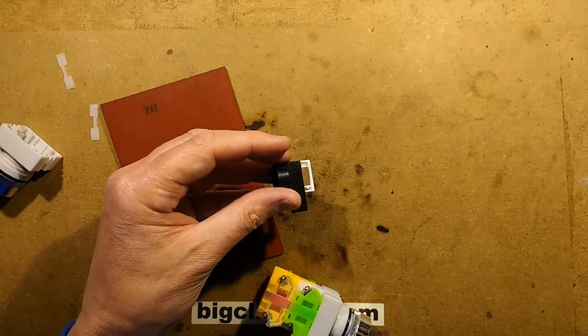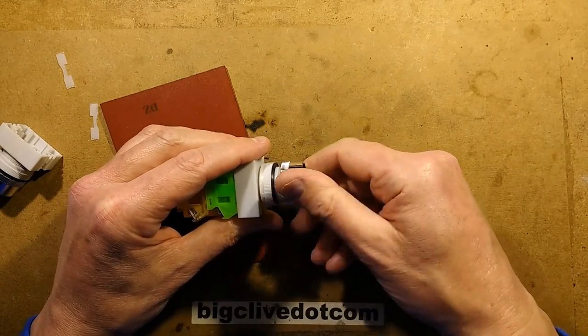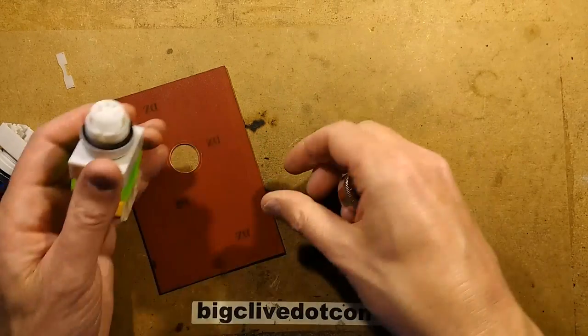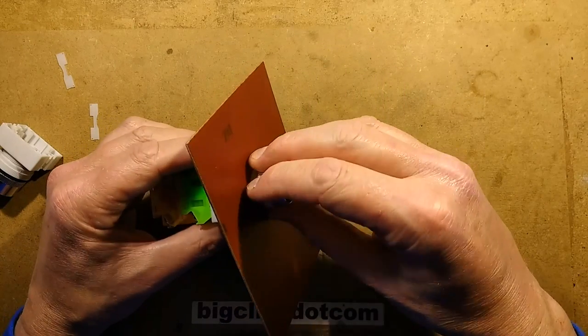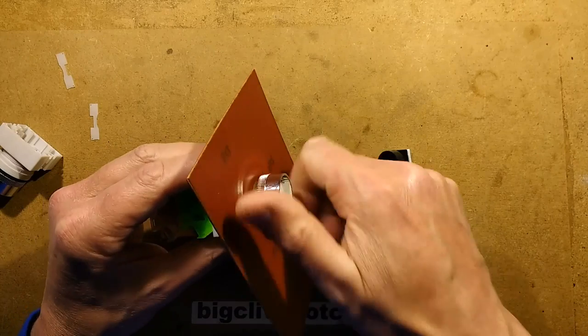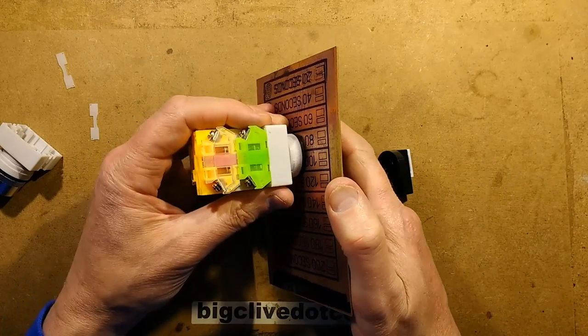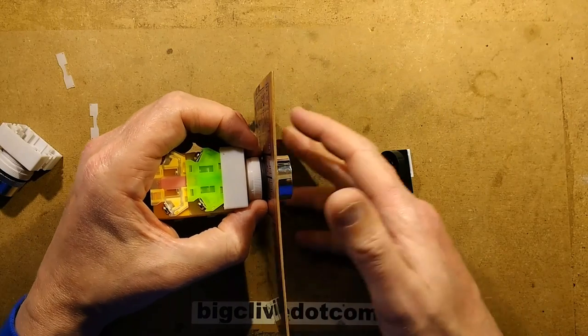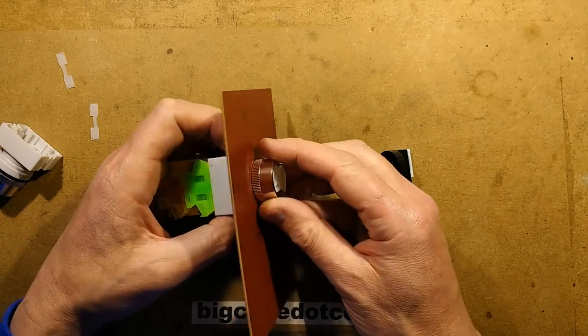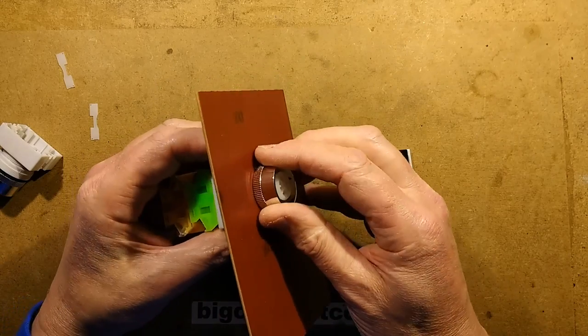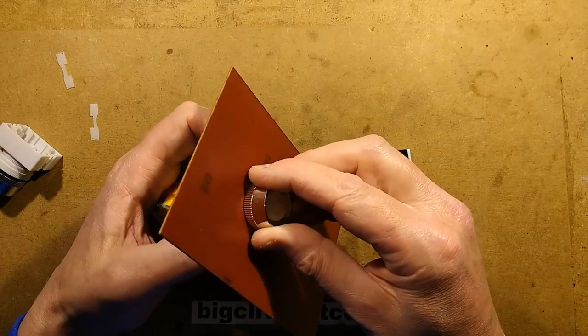So let's zoom back out. To mount this one, pretty much the same arrangement. You've got the bezel here, it goes through a standard 22-millimeter hole. That screws on and you've got a rubber sort of gland at the back of this and an adjustment nut so you can get it into position. And then the rubber gland stops it from slipping round once it's been tightened.